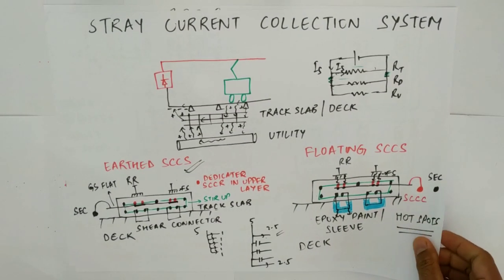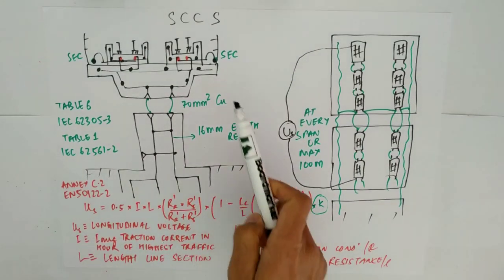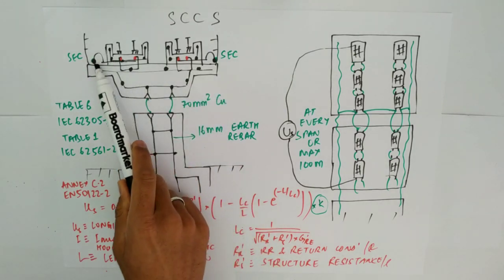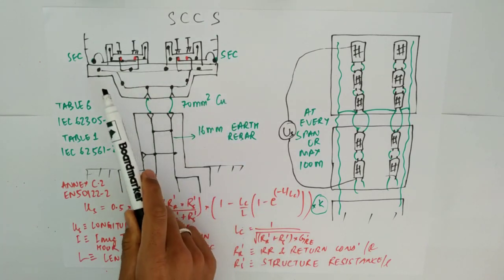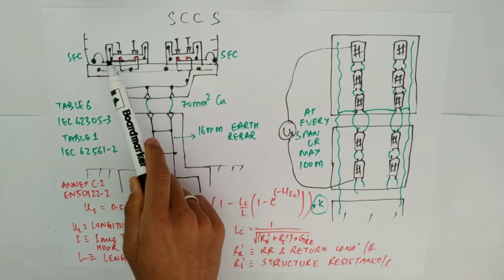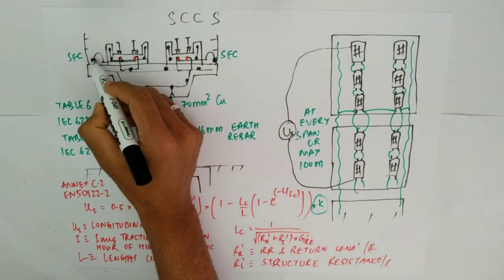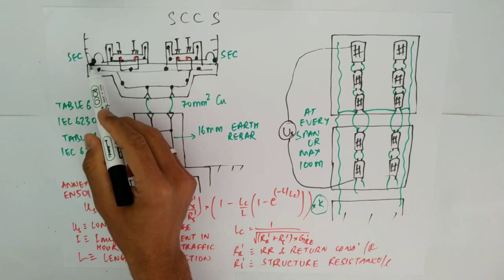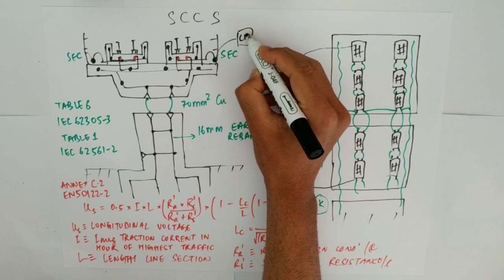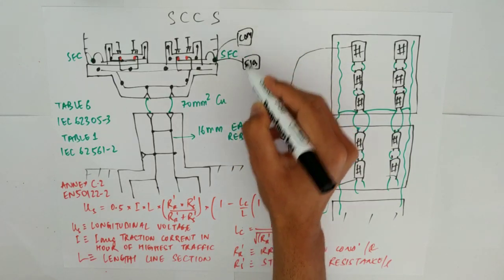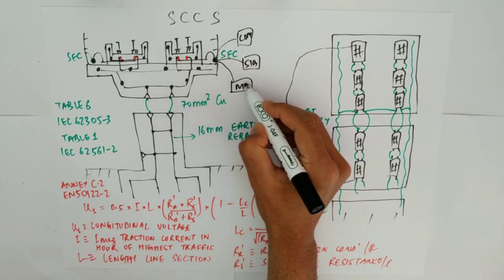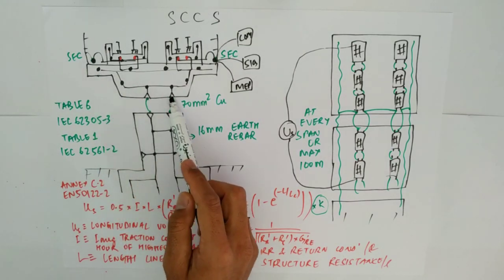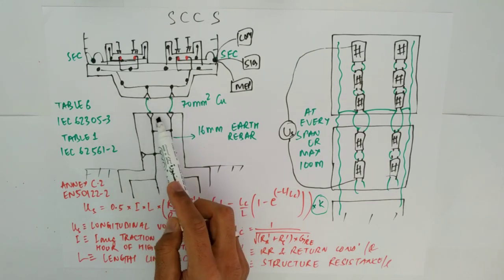For the complete structure, I have drawn the earth stray current collection system. We are having the SEC — that is your structural earth cable. This structural earth cable is also connected to the handrails or the brackets, the cable trays, along with equipments like comm equipments, signaling equipments, and MEP equipments along the path. Apart from that, we are having earth terminals below at the viaduct or the deck and also at the pier cap.